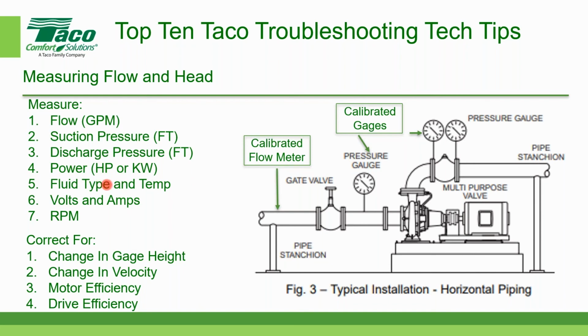It's also important to know what the fluid type is. We've run into this problem a few times. The pump was selected to operate pumping basically clear water, but in fact it was a chilled water system that was pumping a water glycol solution. There was a mistake. They actually designed the system all based on glycol. I think a very common percentage is 30% propylene glycol by volume. But the pump was selected at 100% water, so the pump was consuming more power than originally anticipated, because they had selected it with water but were actually pumping glycol.